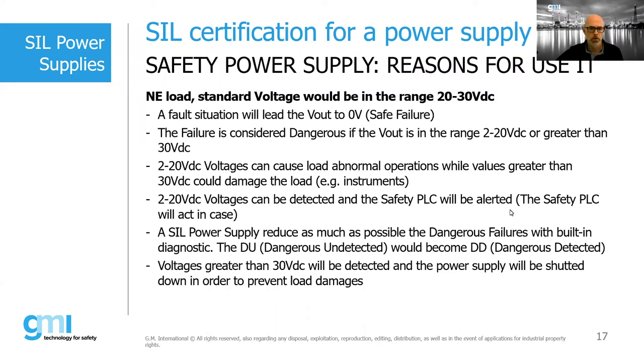Really, there are many applications where the safety function is to energize the load, of the energize to safe or energize to trip type, as in fire and gas systems. A safety power supply is designed to guarantee a SIL2 or SIL3 safety level also for energize to safe applications, which need to energize the load on request. Well, for this type of application, redundancy and overvoltage protection are essential.